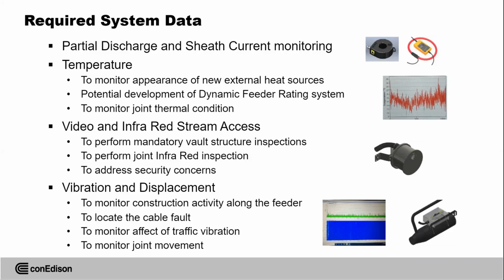Temperature monitoring system, DTS. Of course, we have known DTS for a long time, and we use it for different reasons. For a power cable, DTS will play several roles. One, to monitor the appearance of new external heat sources. We cannot monitor what happens on the street all the time. People or other utilities, other entities can install different systems, can install some ventilation from the subway, for example, in New York City, can install additional power cable, and those heat sources will appear on the profile of your feeder.